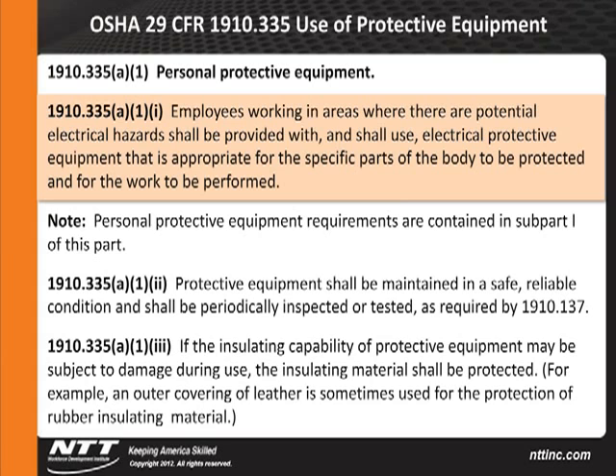Now, if we jump to the end of this particular standard, the last thing we were supposed to do is put on the appropriate PPE and assume the risk. Well, here's the language that comes from OSHA. And again, it's performance-based language. It simply says employees working in areas where there are potential electrical hazards shall be provided with and shall use electrical protective equipment that is appropriate for the specific parts of the body to be protected and for the work performed. Well, I don't see anything in there that tells me what I'm going to be putting on. It says I've got to protect them. The OSHA regulation doesn't really lay out what it's going to be.